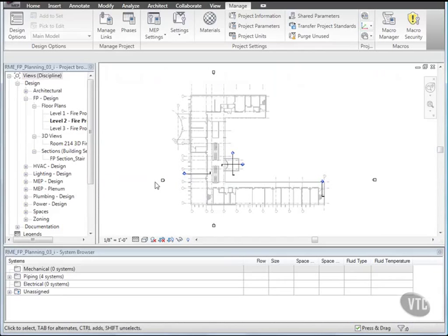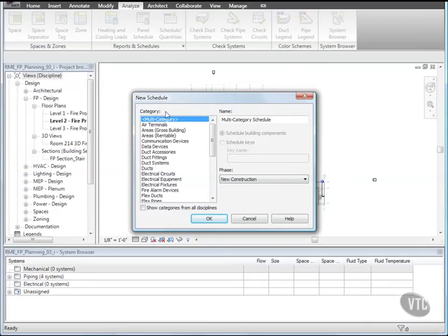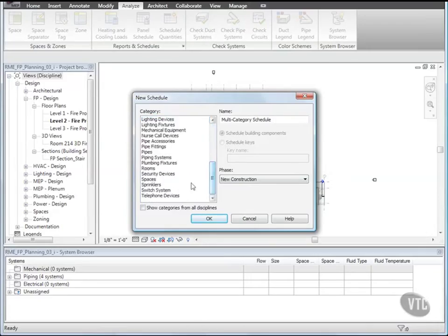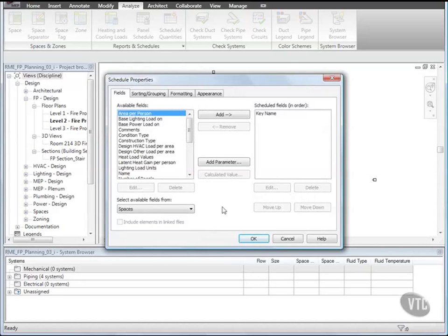Let's create a key schedule. Click the Analyze tab and from the Reports and Schedules panel click Schedule Quantities. In the New Schedule dialog, under Category, select Spaces. For Name, enter Sprinkler Spacing and Coverage Area Schedule. Then select Schedule Keys Properties and for Key Name type Protection Area Construction Type. Then click OK. Next we'll create a schedule parameter.